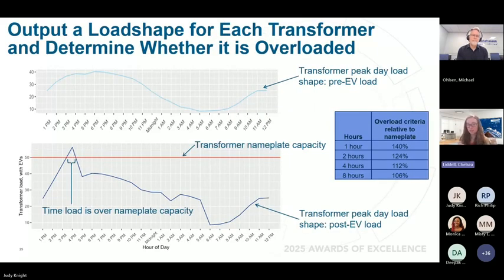This is a visualization of assigning EV load to an actual transformer to check for overload. This is just a toy example with one EV on a transformer. The upper graph is a transformer peak-day load shape, and the lower graph is an actual EV load shape added to that transformer load shape. The red line shows the transformer's capacity, and you can see that capacity was exceeded during one hour in this toy example.